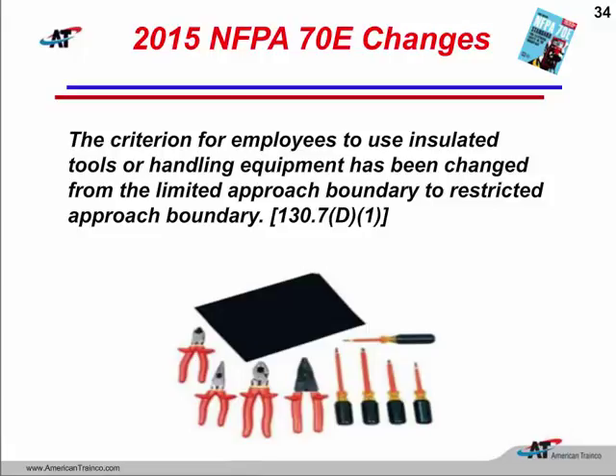The restricted approach boundary, now we're near 12 inches. We are going to be taking covers off. We're going to maybe adjust the torque setting of a piece of equipment. So that's where the 1,000-volt tools would come in. So restricted approach boundary is going to trigger now also 1,000-volt rated tools for our equipment.